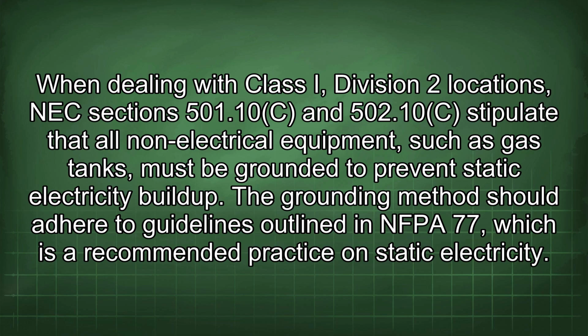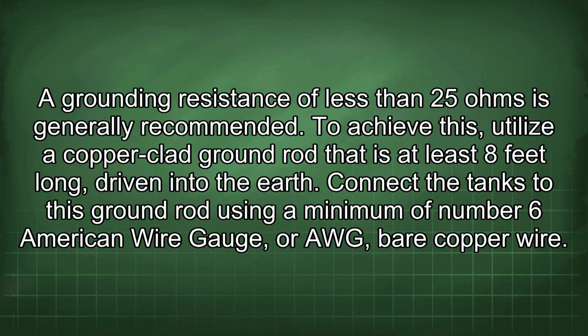The grounding method should adhere to guidelines outlined in NFPA 77, which is a recommended practice on static electricity. A grounding resistance of less than 25 ohms is generally recommended. To achieve this, utilize a copper-clad ground rod that is at least 8 feet long, driven into the earth.